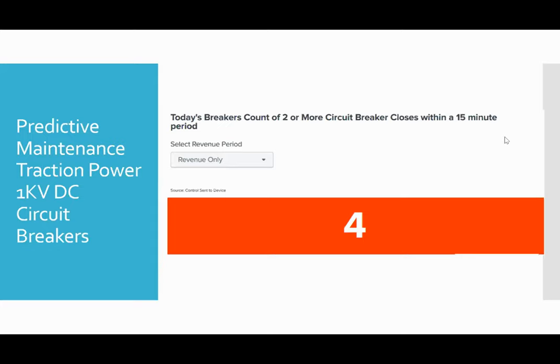This is how they find out about it today, a recent development for us in the last five or six months. We now have these alerts and can drill down into, say, this number four to see the types of problems, then immediately dispatch maintenance crews to those locations to do the PM or check the breakers for visual indications something is going wrong. This goes back to our primary goal: moving us from reactive preventative maintenance to creating algorithms like this that prevent catastrophic disasters.